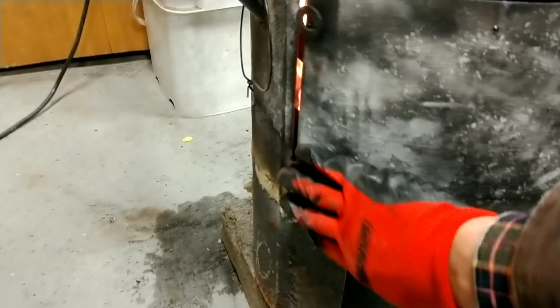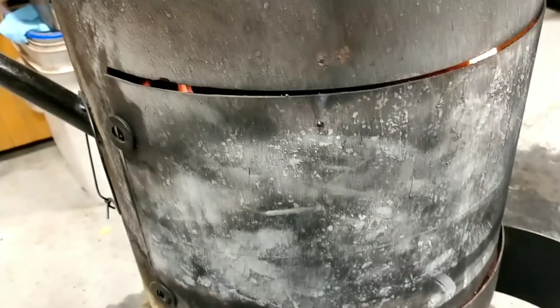So, now that we've established flame, we're going to close our burner door, not our air door. Our air door has to stay open. And listen to this sound. You'll hear it change. You hear that? So we're now burning on waste oil, and let's take some temperatures to see how this thing comes up in heat.